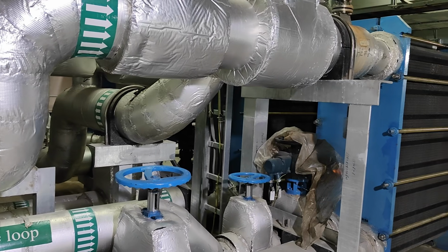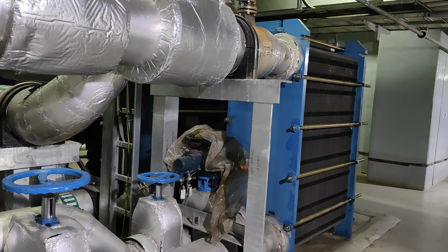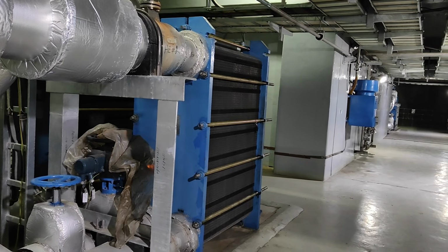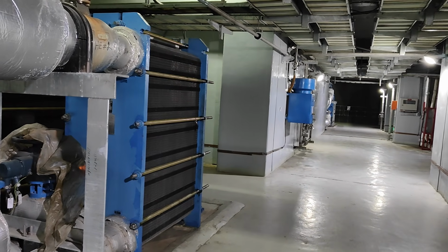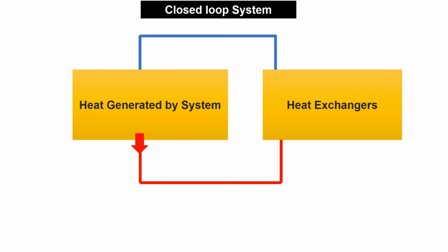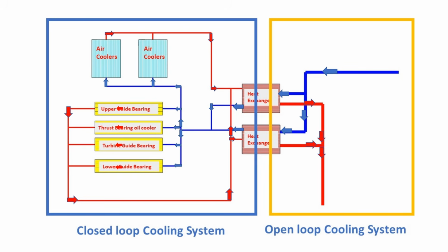So this is the most important component in the entire cooling system. The plate heat exchanger, think of it like two highways of water separated by thin metal plates. On one side, hot, clean cooling water arrives from the generator and the bearings, and on the other side, cold river water flows from the open loop. Heat passes through the metal plates, but the water never mixes. The dirty river water carries the heat away, and the clean water becomes cold again, ready to cool the machine once more. This process repeats continuously every second while the unit operates.